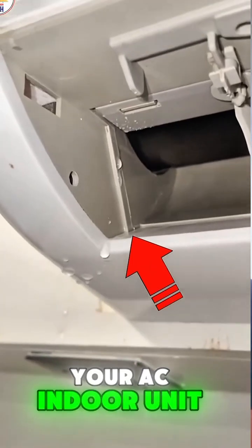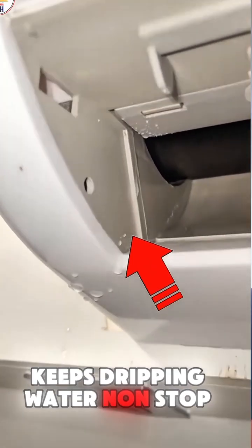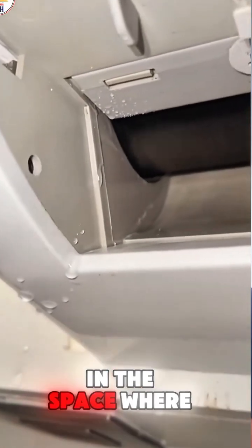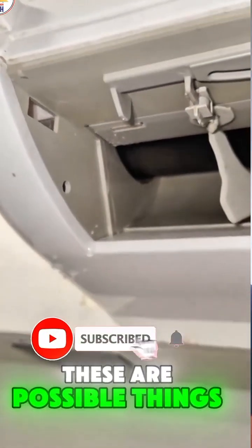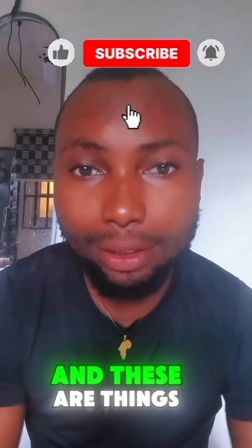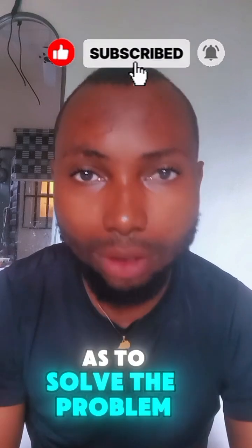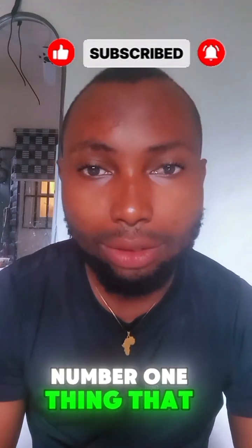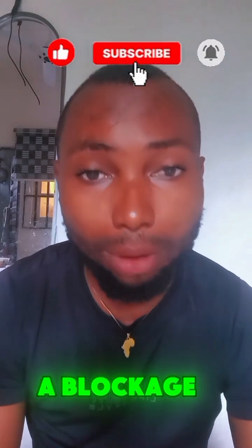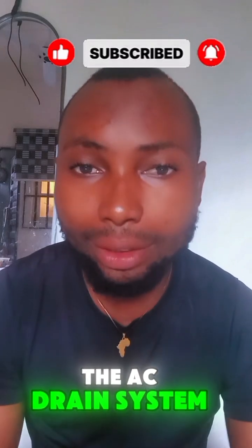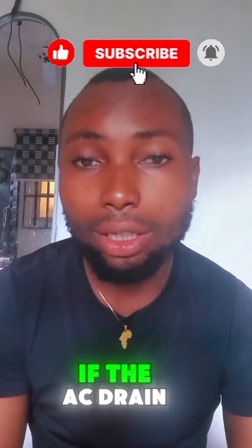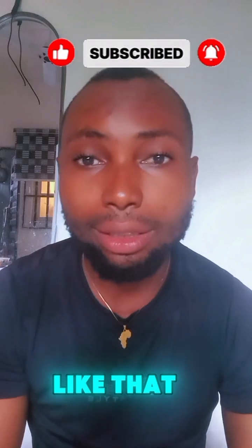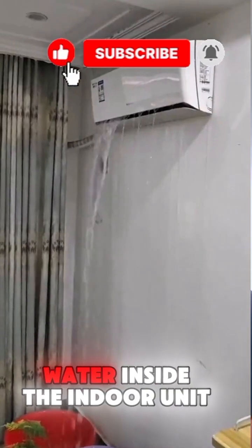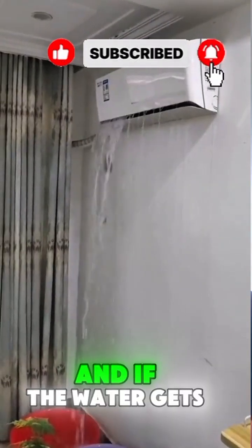Your AC indoor unit keeps dripping water non-stop in your room or in the space where it is being installed. These are possible things that could be the cause, and these are things you need to do to solve the problem. Number one thing that could be the cause is that the AC drain system, the AC drain pipe, has a blockage. If the AC drain pipe has a blockage like that, it retains water, accumulates water inside the indoor unit. And if the water gets too excessive, it starts dripping inside the room or space that it is being installed.